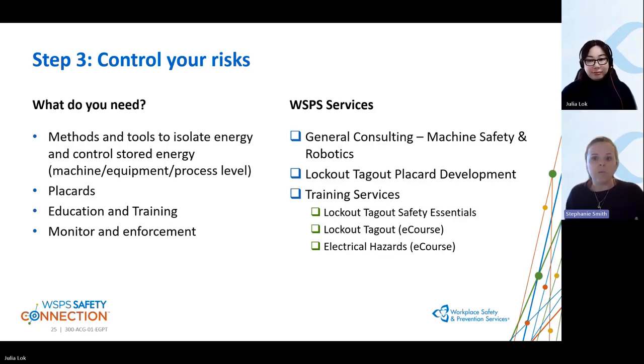When we look at lockout placards specifically, we're looking at full zero energy. That means taking the machine into a zero energy state, where no energy is present. Everything is either isolated, blocked, bled off, or controlled in some manner. It's like the safe zone you go into for full maintenance activities, housekeeping, or any work that can't be handled by another means of control.